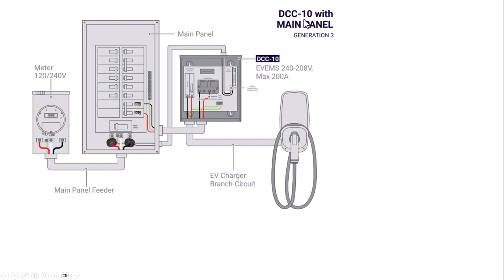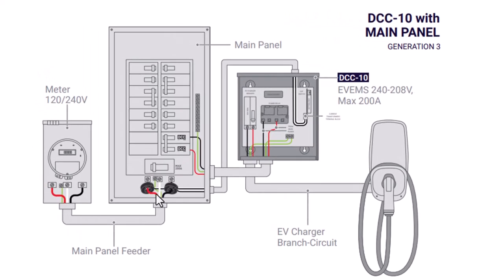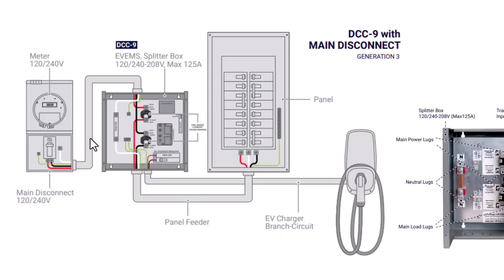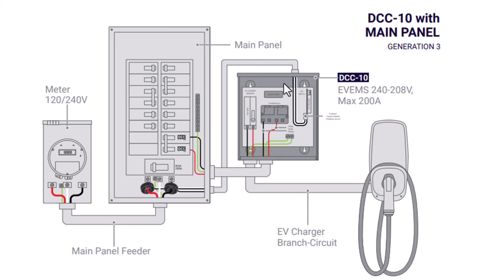All right, so now I'm going to go to the next one, which is the DCC10. So as you can see here, it's not actually in line with the main service, just like in this case, you see it's in line with the main service. For the DCC10, it's actually off to the side and it gets connected. So it's not in line to this, it's actually to the side and it's being powered through a breaker in the panel. So you can see the power goes to the relay, which basically will switch the power to the EV or basically disconnect the EV power so that all the power could flow through the main.